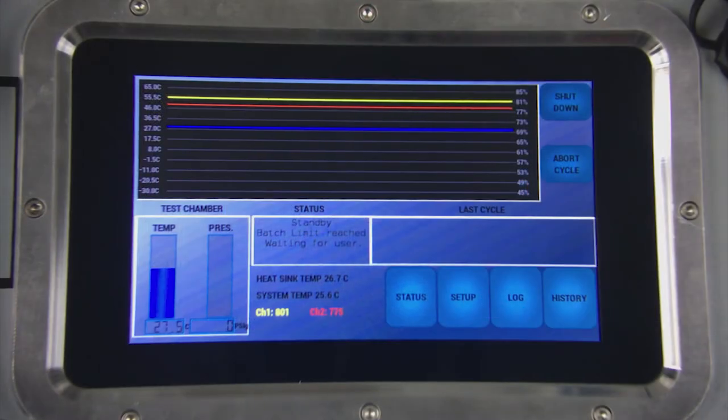The status screen is the main default screen during operation of the unit. Here you will find several areas that indicate the status of the analyzer and measurement cycles. The temperature indicator shows the current temperature of the mirror. The pressure indicator shows the pressure at the measurement cell which should match the input pressure. The status box shows the current state the analyzer is in before, during, and after measurements. It will indicate if the system is initializing, cooling down, warming up, or waiting for thresholds to be met in order to begin the next cycle. Below the status box you will find the heat sink and system temperatures as well as signal counts for detector channels 1 and 2.